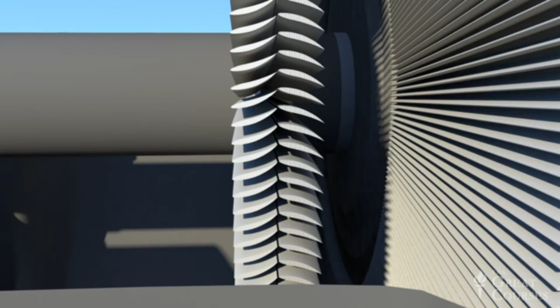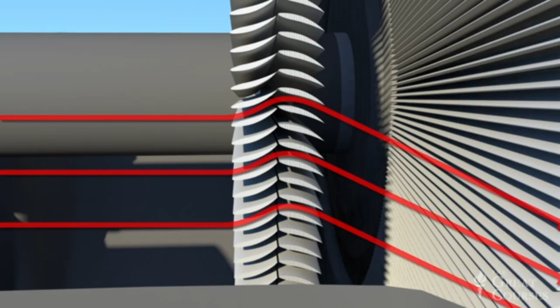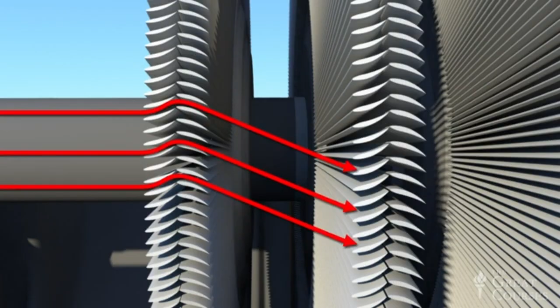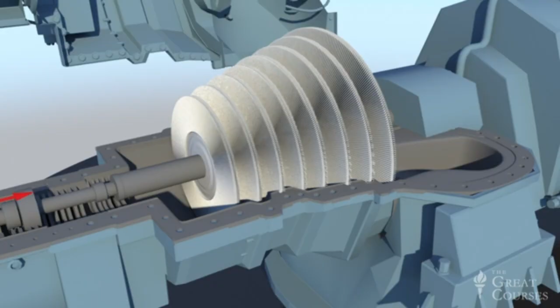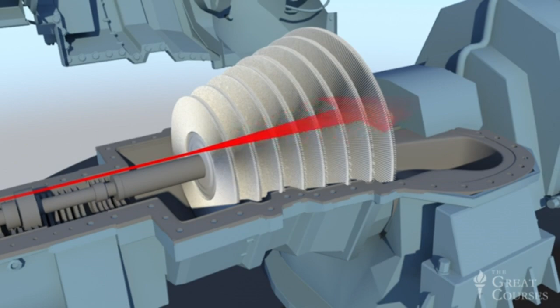As high velocity steam emerges from the stator, it passes through the angled blades of the rotor, which deflect the steam as you see here. As the steam changes direction, it applies a force to the blades, and like a windmill, the force turns the rotor. The steam, now with a little bit less internal energy, passes to the next stage, where it's accelerated by the second stator before imparting energy to the associated rotor. Because the steam expands through each stage, the rotors need to be progressively larger to capture the steam's energy as efficiently as possible.